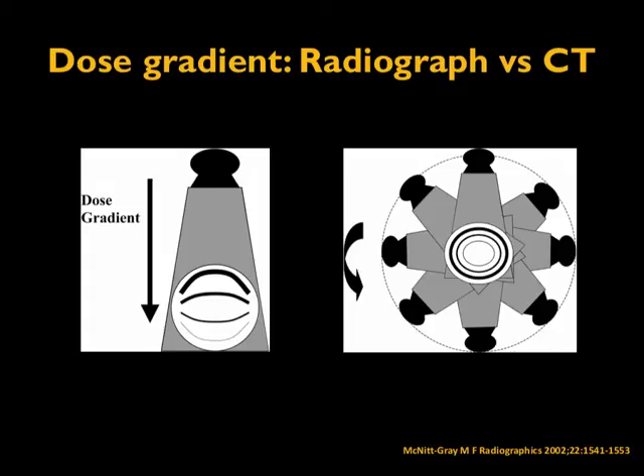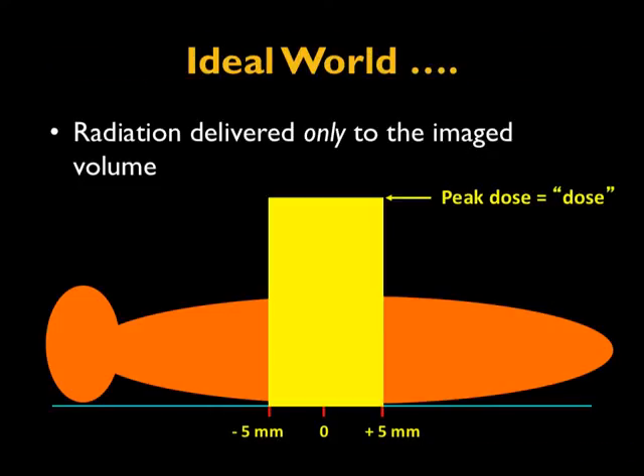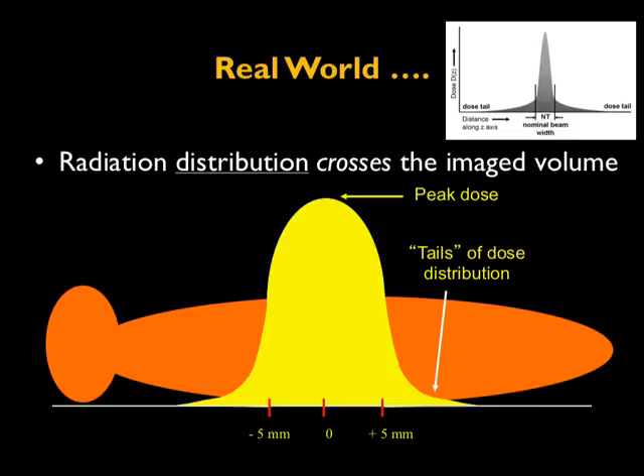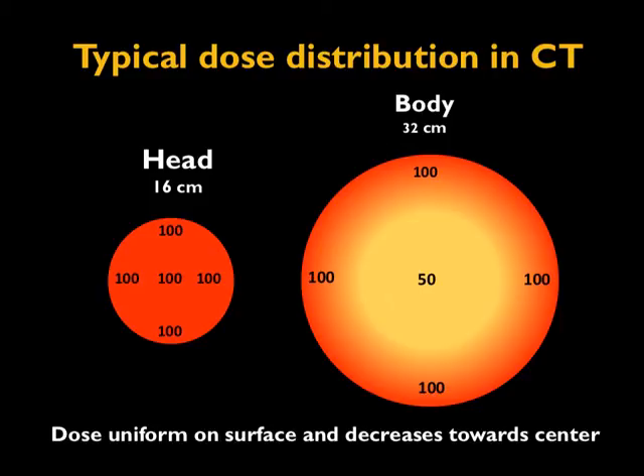It is important to understand the distribution of CT dose and how it translates into dose measurement. Ideally, the radiation dose delivered in CT should be like a square block — if you use a 10 mm slice thickness, the anatomy exposed should be exactly 10 mm. However, in the real world, the distribution is more like a bell curve: the actual peak dose contributes to only a small portion of the slice, with a tail end. Because of this, we also need to understand how CT dose distribution varies for different patient sizes.